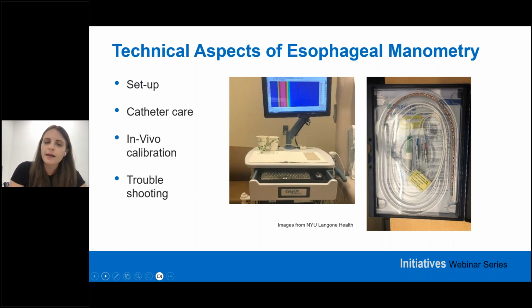This is what a properly calibrated catheter would look like. If there were any issues with some of the sensors, there would be impingements in that area of the catheter where the sensor was malfunctioning on that column of pressure. But since this is all straight up and down, we know that it was functioning properly.